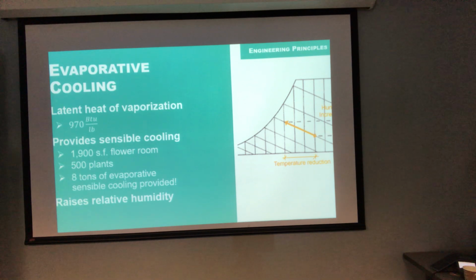And that creates a really weird, what we refer to as a sensible heat ratio. A room like this was designed for probably a sensible heat ratio of 0.8, meaning most of what has to happen in this room is we've got to cool it off, not a lot of dehumidification. We see flower rooms with sensible heat ratios as low as 0.4, meaning there's very little cooling that has to take place in that room, but there's a ton of moisture that needs to be removed. That's a problem because the mechanical systems that serve these types of spaces are meant to serve sensible heat ratios of 0.7, 0.8, 0.9. They're not designed to serve sensible heat ratios of 0.4, 0.5. So when you take typical commercial HVAC equipment and put it in indoor cultivation facilities, you've got a real mismatch between the equipment's ability and the loads of the space.